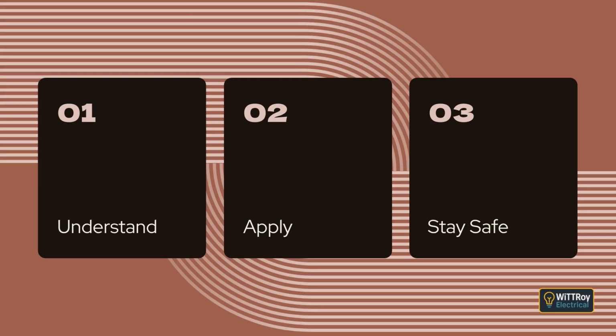Clause 1.5.7, Basic and fault protection using extra low voltage, SELV and PELV. SELV and PELV systems can provide both basic protection and fault protection, but only when certain conditions are met. The first condition is the voltage limit. The system must be arranged so that it cannot exceed extra low voltage levels of 50 volts AC, or 120 volts ripple-free DC. The second condition is separation from other circuits. These circuits must be kept separate, both electrically and physically, from each other and from any higher voltage circuits. For SELV systems, the live parts must not be connected to earth or to any protective earthing system used by other circuits. For PELV systems, if a person can touch the live parts, the voltage must always remain within the limits allowed for that particular environment.